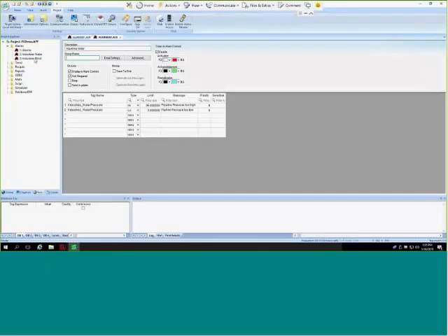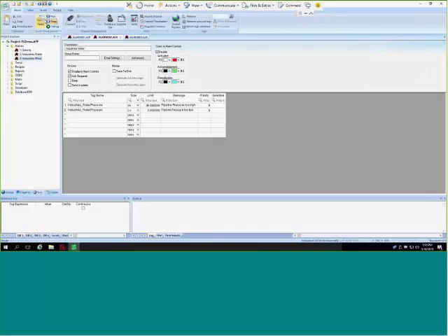The alarms that we'll be connecting to are in these three different groups. So we've got the alarms groups, these are simulation tags, and we've got the water tags and the wind tags. I'm not going to bring these water tags in because they go in and out of alarm constantly so fast that we probably won't be able to do anything with them. So what we're going to do is we'll configure Win911 to pull alarms from this group and this group. And then we'll send those notifications out, reply to an email, and acknowledge one of those alarms. So I'll go ahead and run the project.